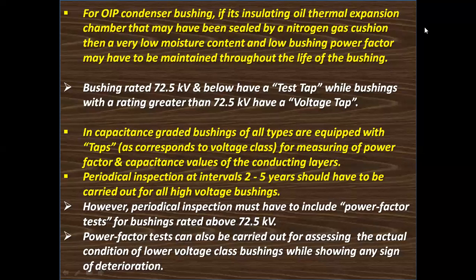Periodical inspection at intervals of 2 to 5 years has to be carried out for all high voltage bushings. However, periodical inspection must include power factor tests for bushings rated above 72.5 kV. Power factor tests can also be carried out for assessing the actual condition of lower voltage class bushings showing any sign of deterioration.